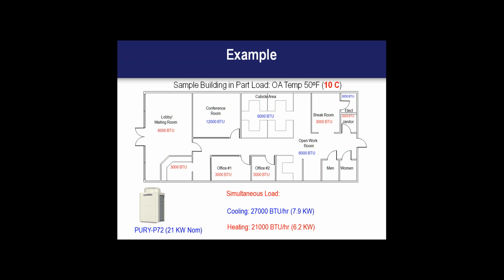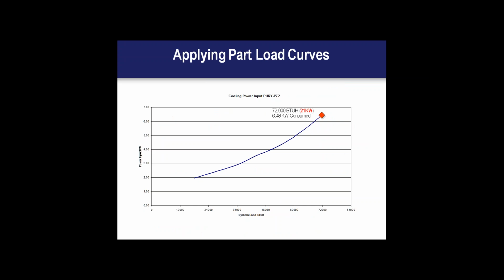Again, the dominant load at this hour is the cooling load, 7.9. So that's what dictates the compressor operation and the demand from the outdoor unit, not the heating load. So if we start looking at these ratio curves, if we were at a fully loaded state on a 95-degree day, we would consume around 6.48 kW. Since we're at a reduced load state of 7.9 kW cooling load, that correlates to 2.38 kW roughly.